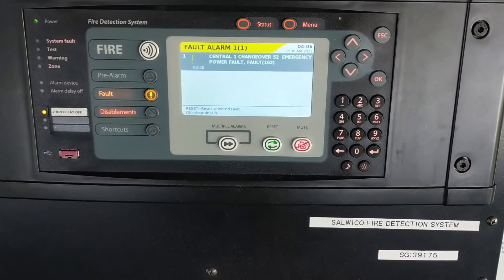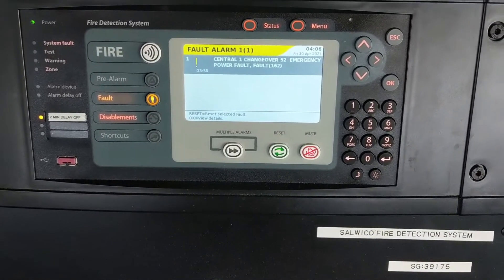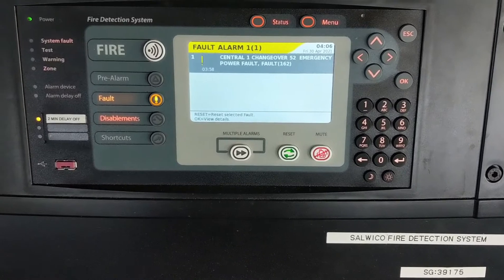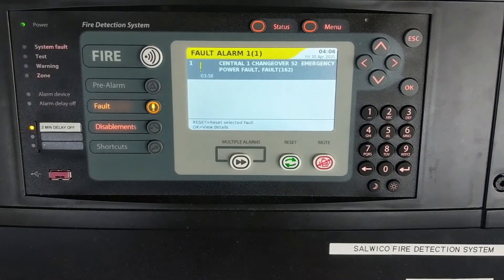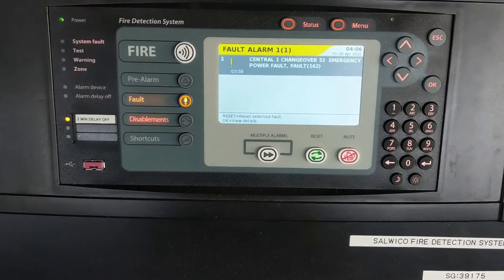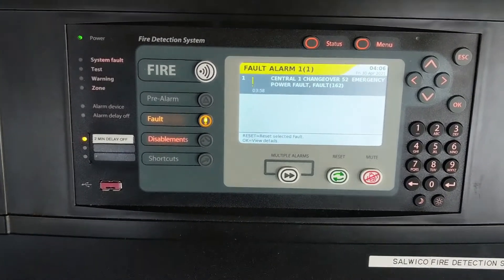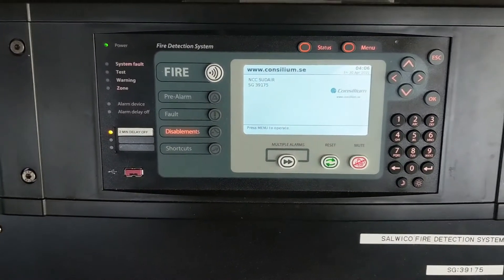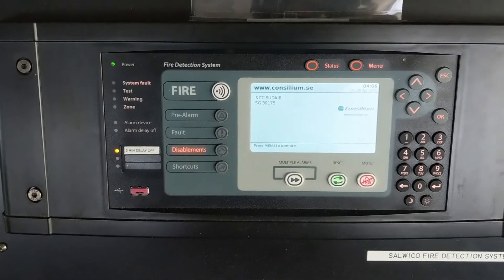Let's investigate what alarm came on the fire control panel. We can see central one, changeover S2, emergency power fault. This is fault 162. We can reset it — and now the reset is done, which means everything is working fine.